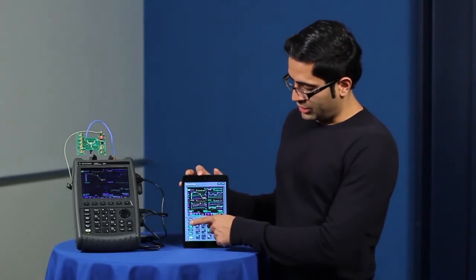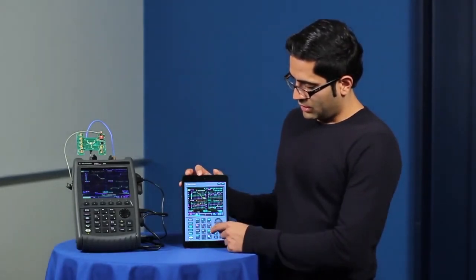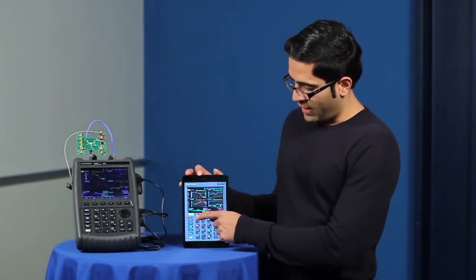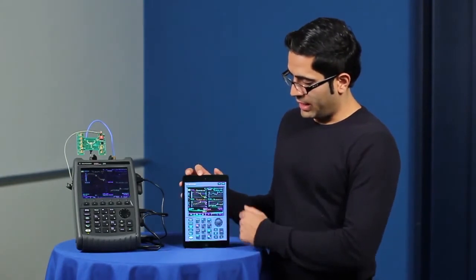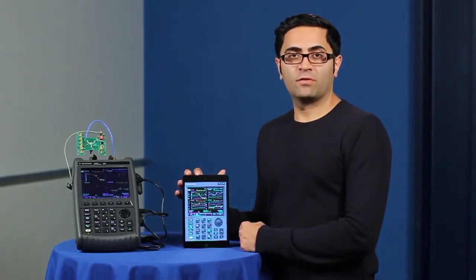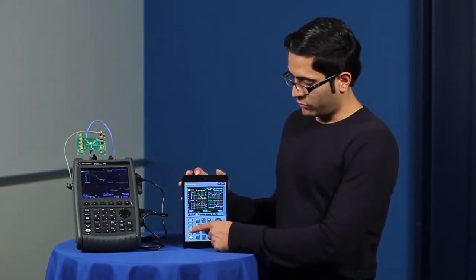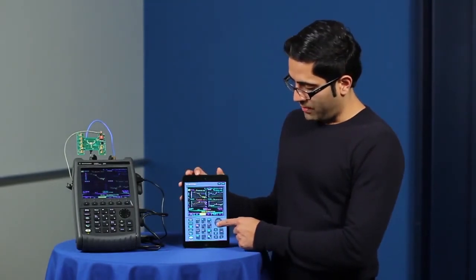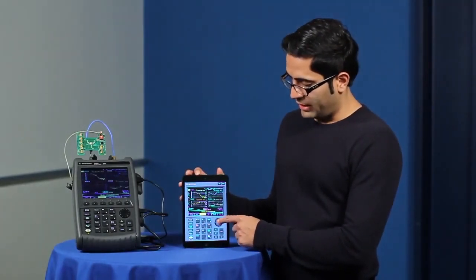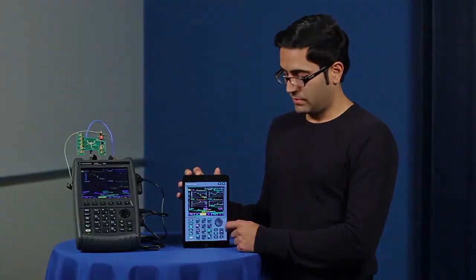Here I would like to change the frequency. I'm going to change my start frequency to 5 GHz. And you see how fast and smoothly that works. You can also use the marker with the knob and set the marker at any desired frequency.